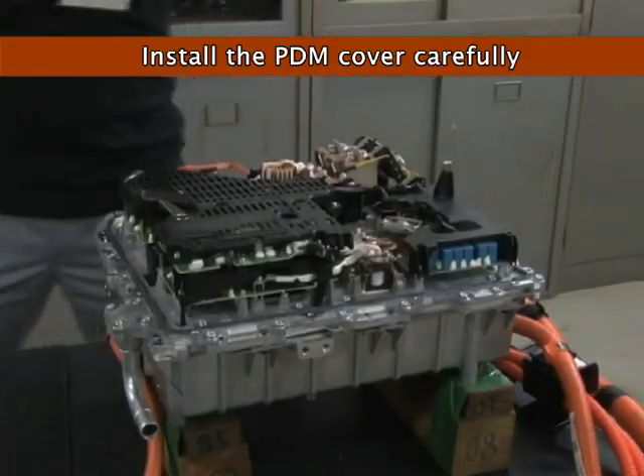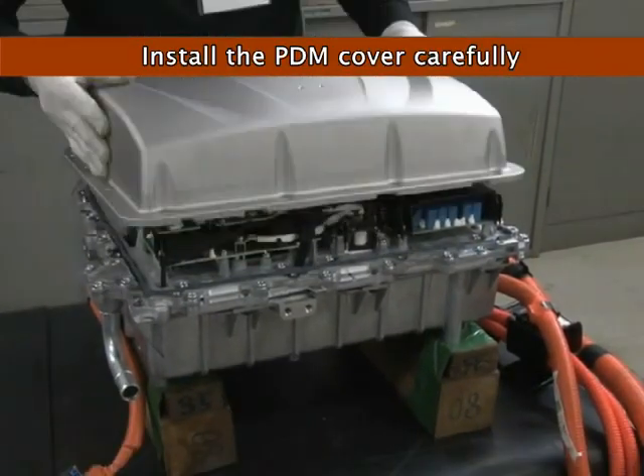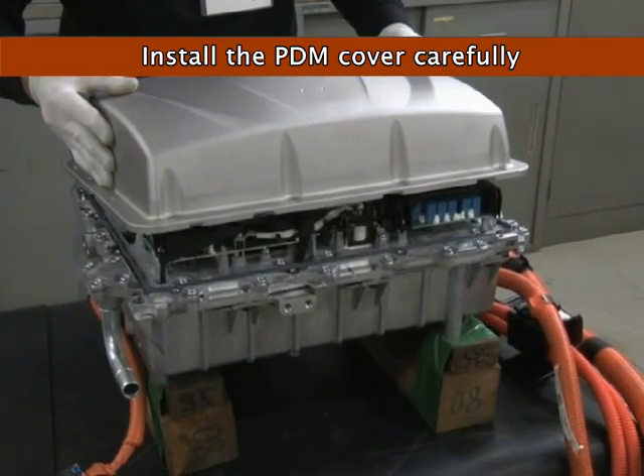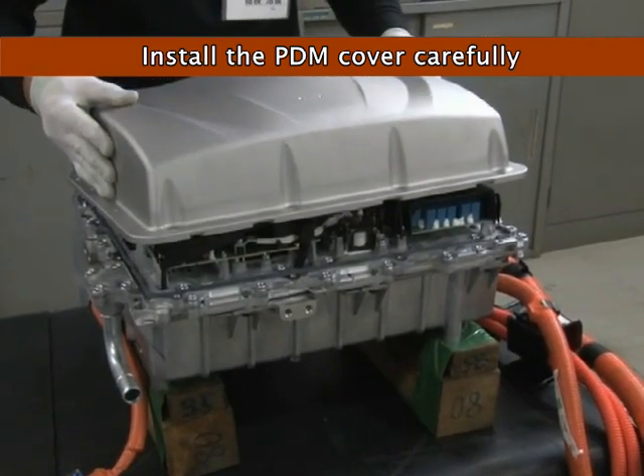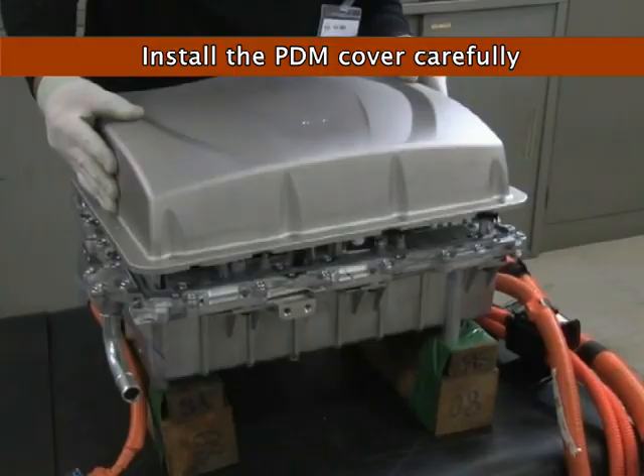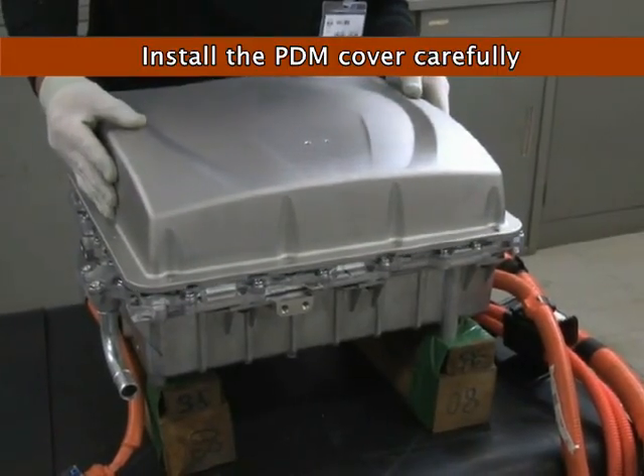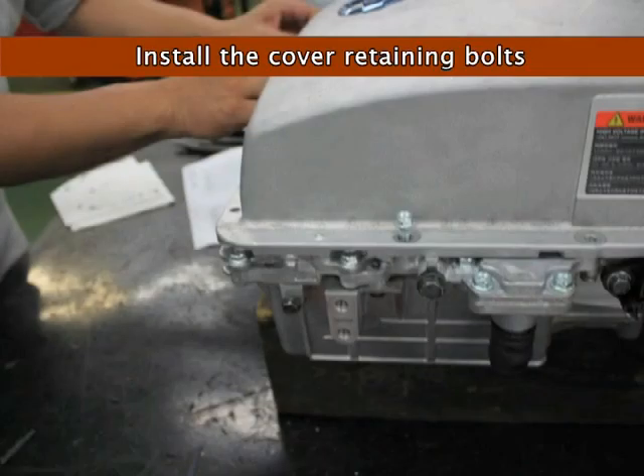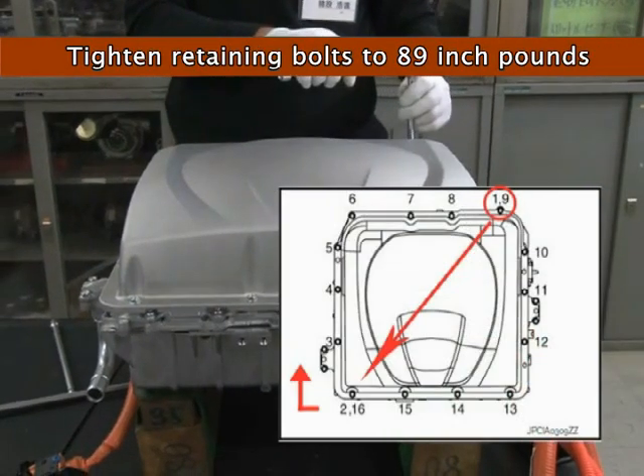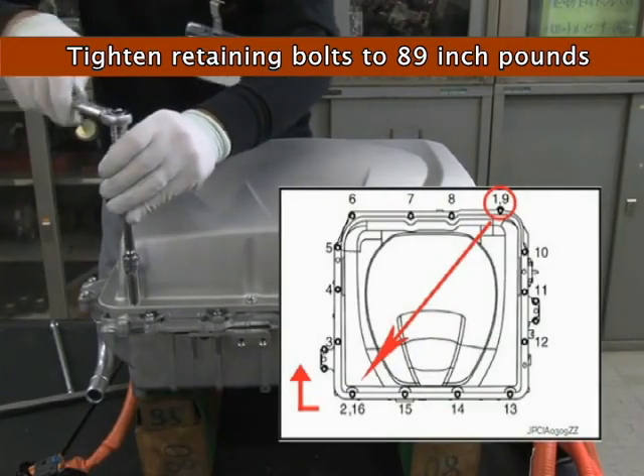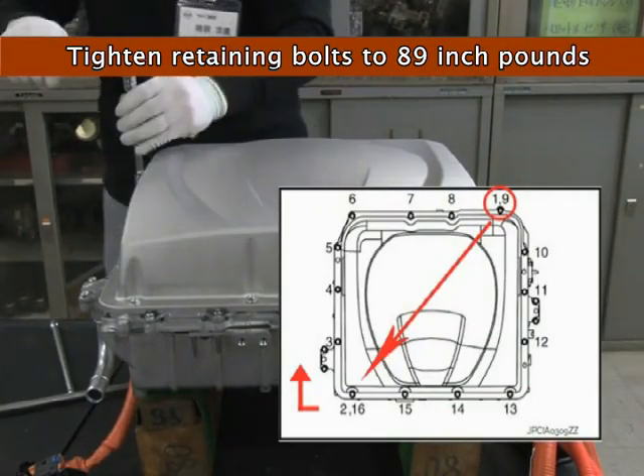Remove the protective cover and install the PDM cover carefully. Lower the cover straight down onto the housing. Install the retaining bolts for the PDM cover and tighten by hand. Then tighten the securing bolts to 89 inch-pounds using the order shown in the service manual.